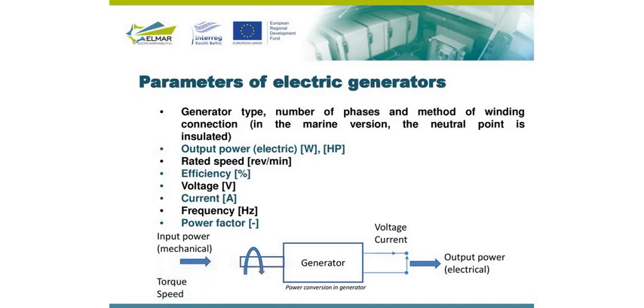The electric generators are characterized by basic parameters. We can have a generator type. Typically, the generators are three-phase synchronous type, but other types are also possible. The three-phase generator needs to have a defined winding connection, and for marine applications, the neutral point of the generator is insulated. This is detailed information, but important from the point of view of usage of this generator, compared to the units used on land.